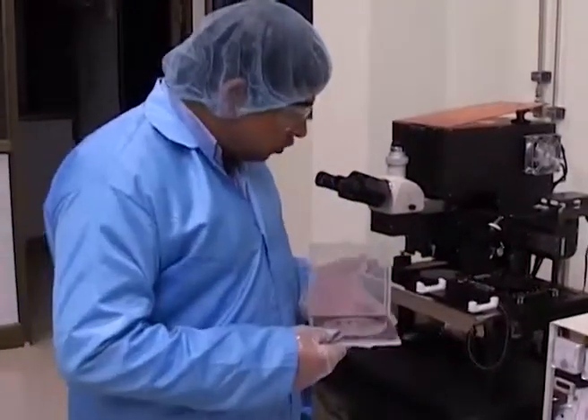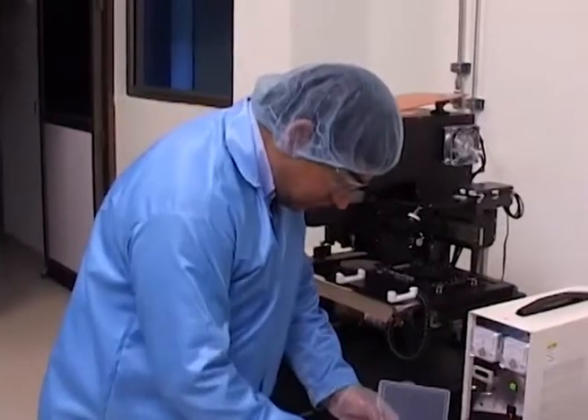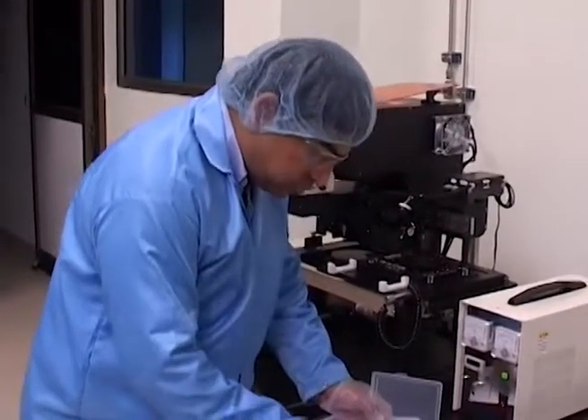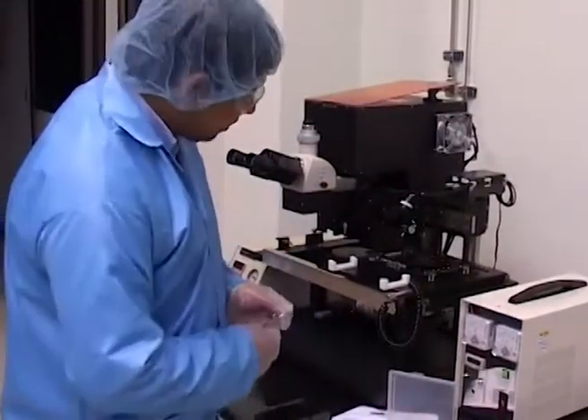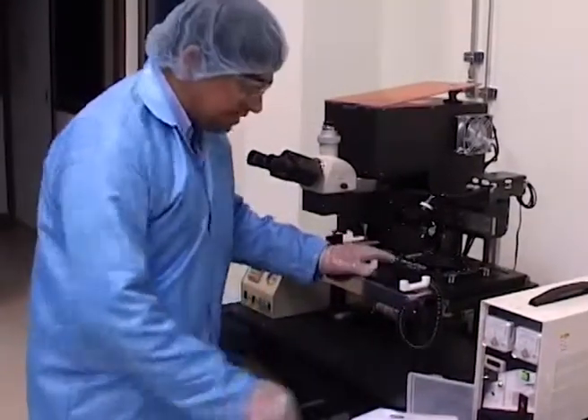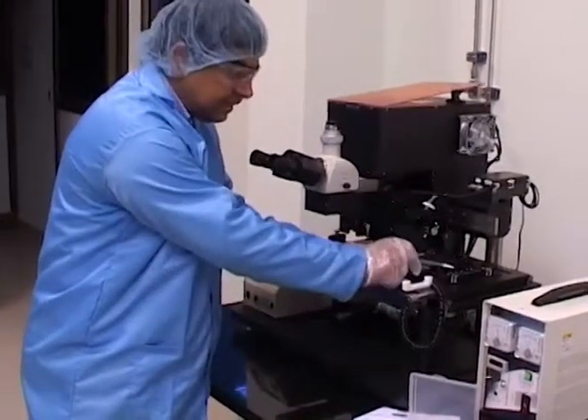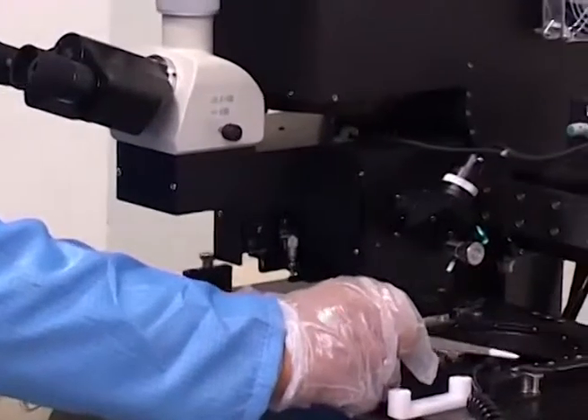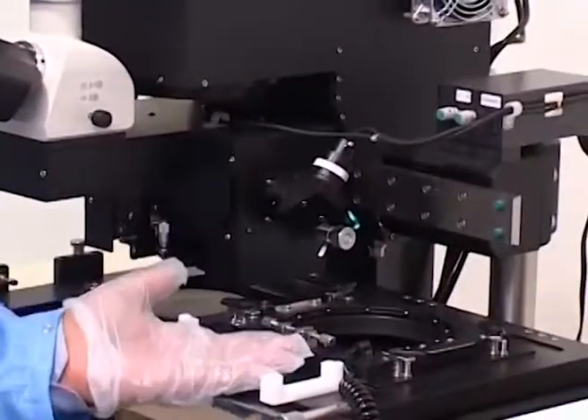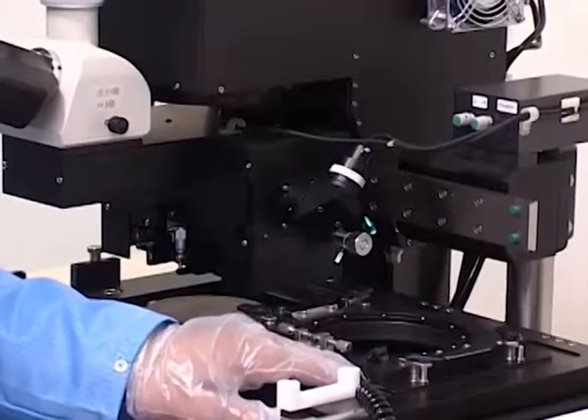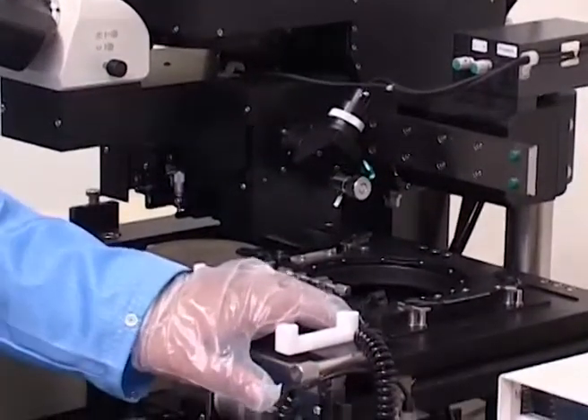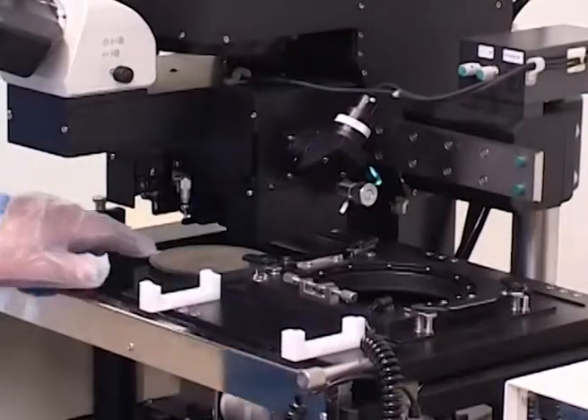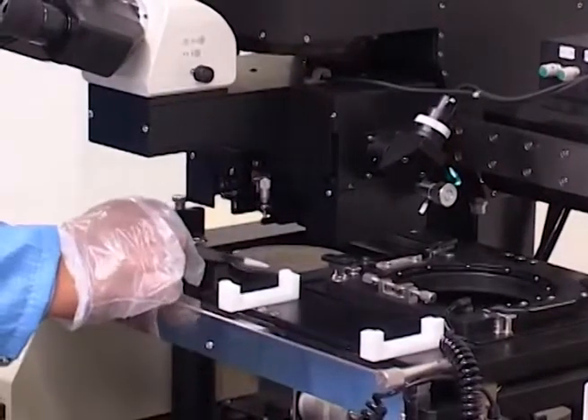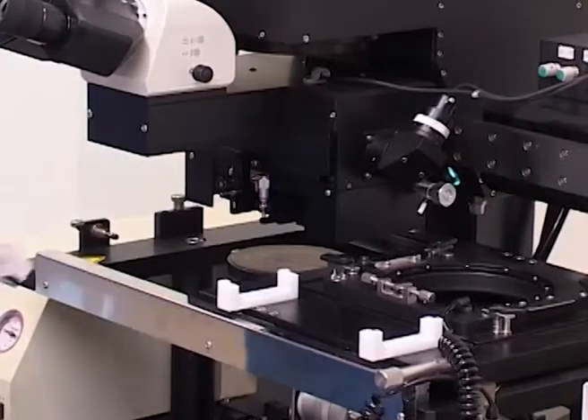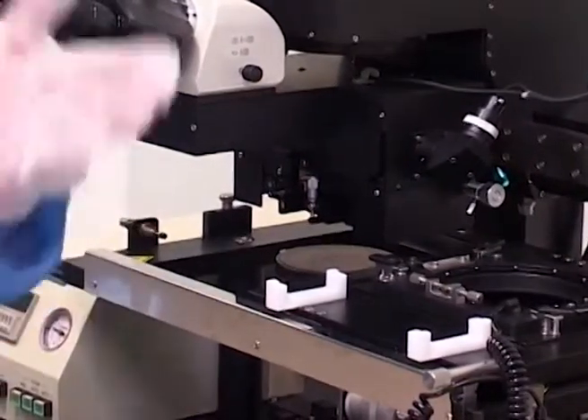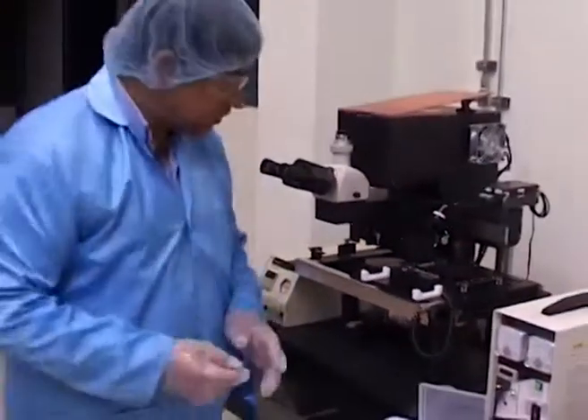So what I'm going to do now is to tell you how to use the lithography setup to actually do alignment and exposure. So here we have something called a mask holder, which is actually this region here. The mask is really sitting on the bottom side of this particular holder, and it is facing the wafer, which would be placed somewhere here. This is the wafer stage, and the idea is to be able to precisely align the hard mask over the wafer surface.